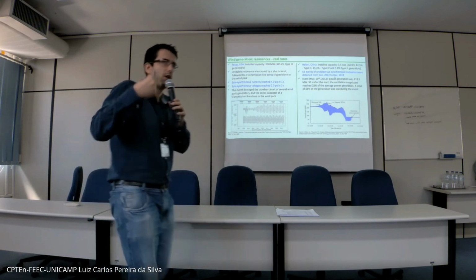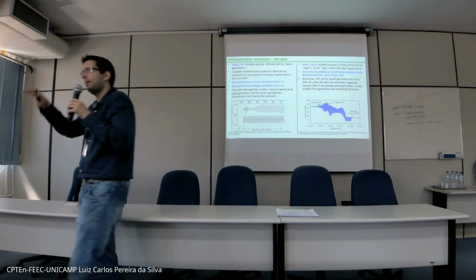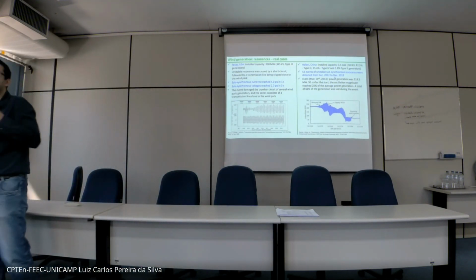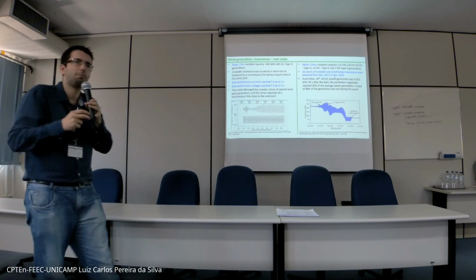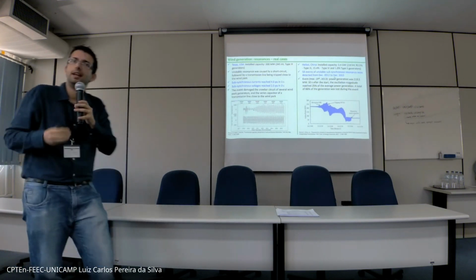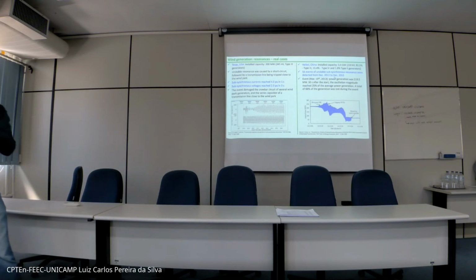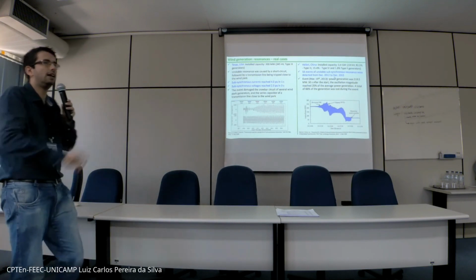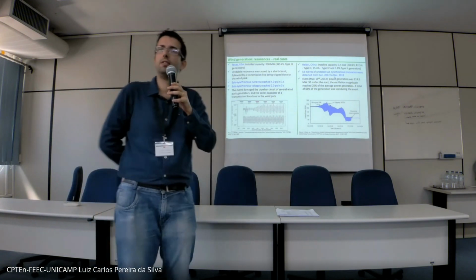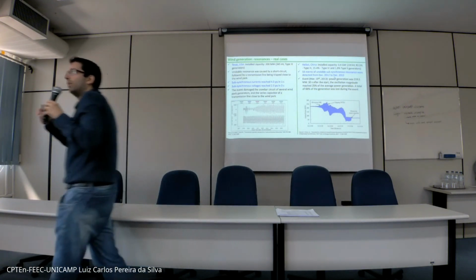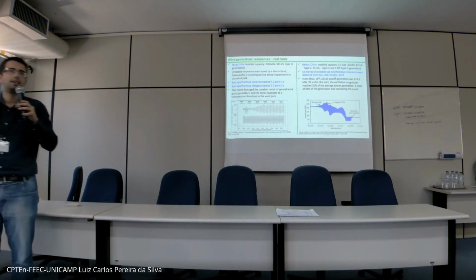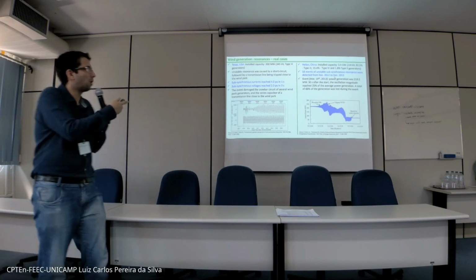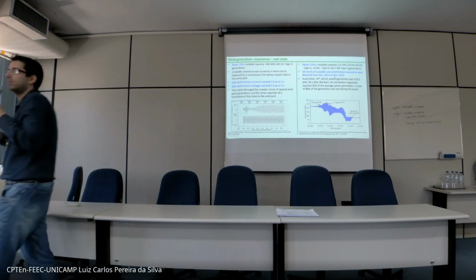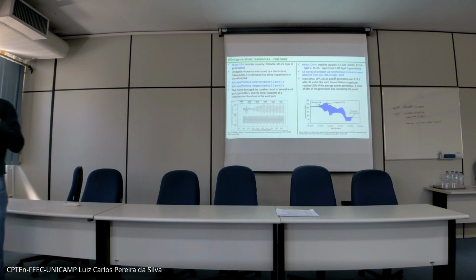One of the main issues behind this is the integration of power electronic-based generators - they have some issues with resonance damping, which can decrease resonance damping and make the system unstable. It's essential to detect these events as early as possible, and power quality meters allow us to do that.